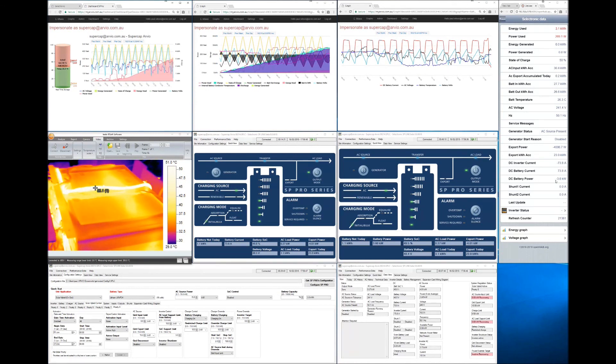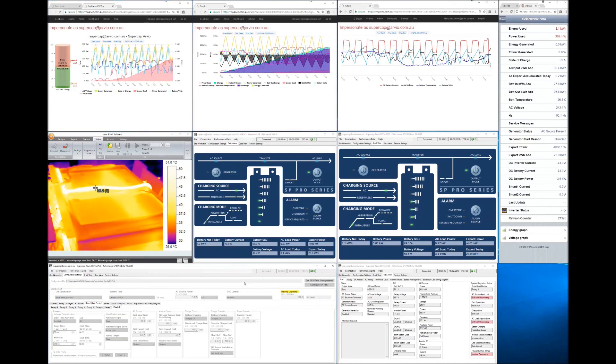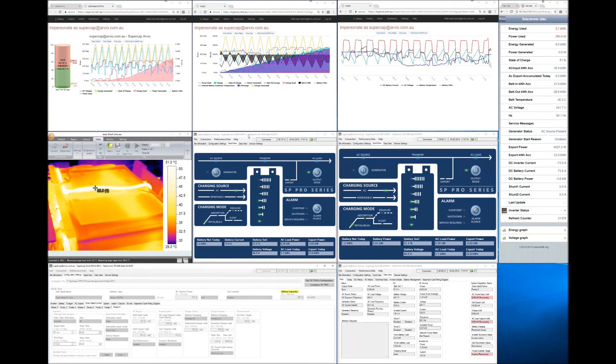You've got here live recording. Thermal camera filming the conductor getting hotter as we charge. You might see this fall away a little bit now because we're now starting to discharge. So we're charging from the grid at 74 amps. This logging software is SP-Link which is a program native to the SP-Pro inverter made in Melbourne, Australia. And it's a great inverter for letting us do these really high energy tests.